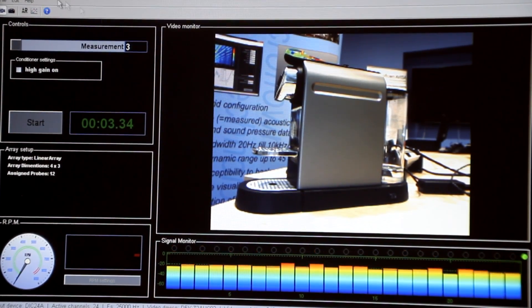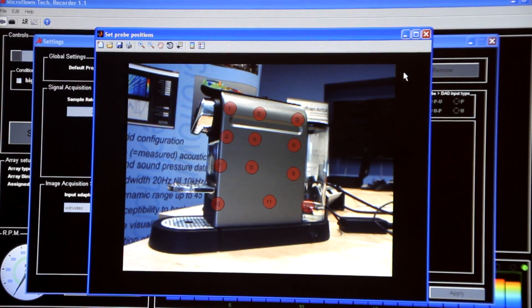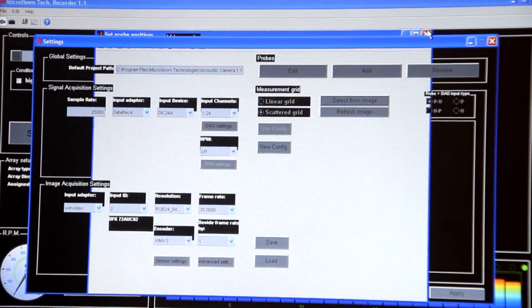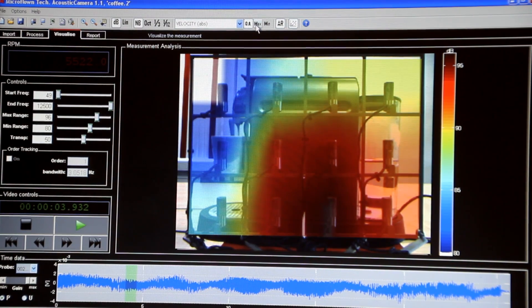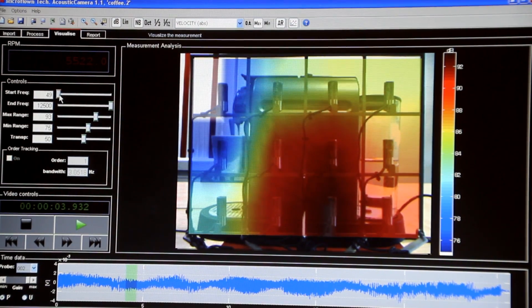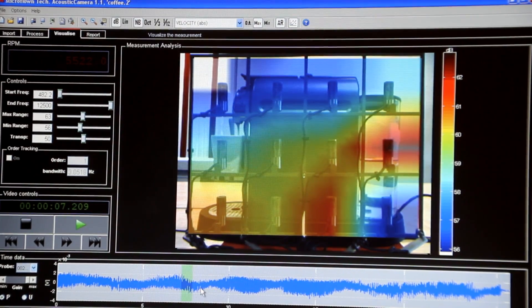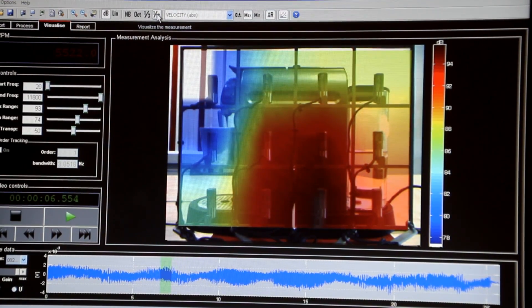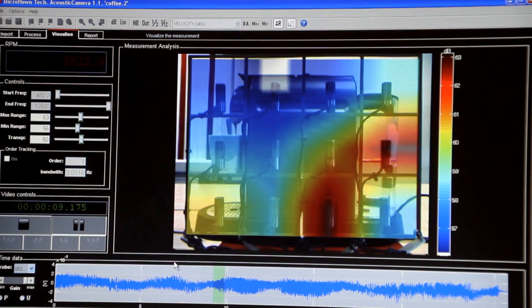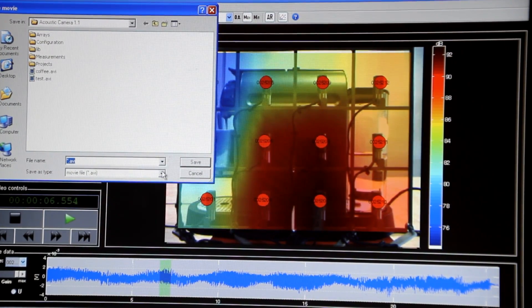The software is divided into recorder and processing. First, all the data are stored on the hard drive, then it is possible to process all the time history and use an RPM reference sensor for order tracking. In the Visualise tab, it is possible to show color maps of velocity, pressure, and intensity in certain frequency bands, spectrograms over time for each probe, octave and third octave. Also, it is possible to play back the audio of each probe and create video in AVI format.